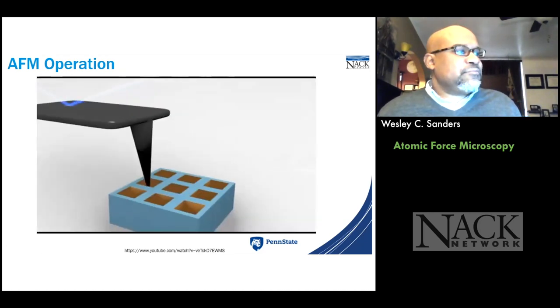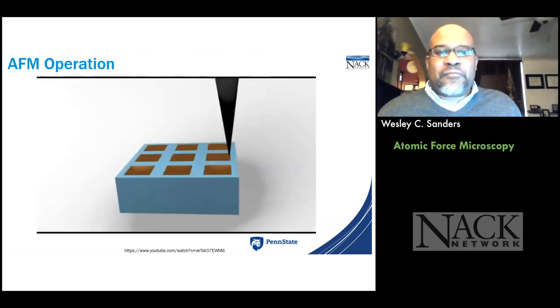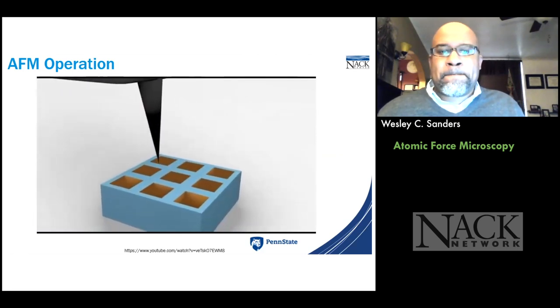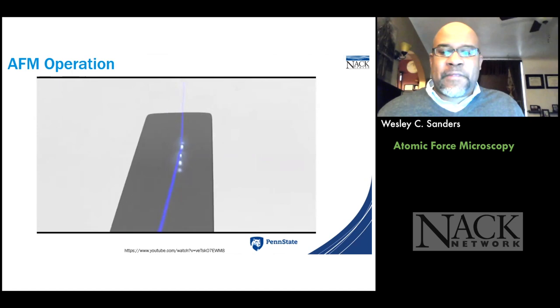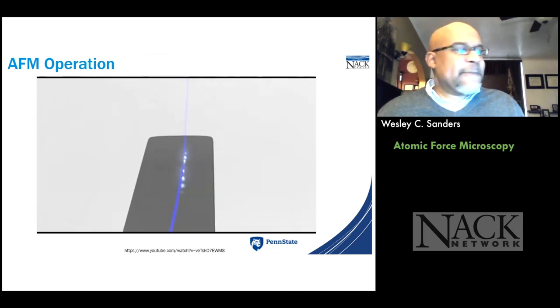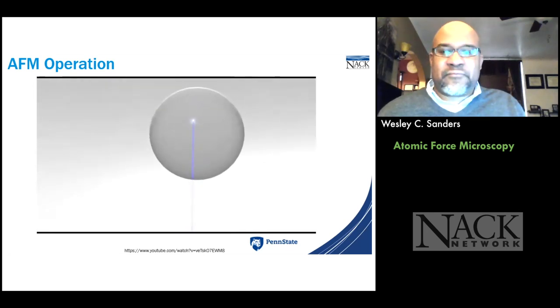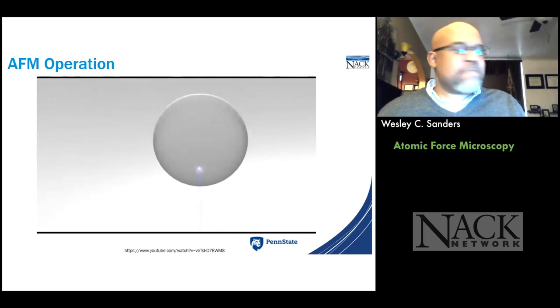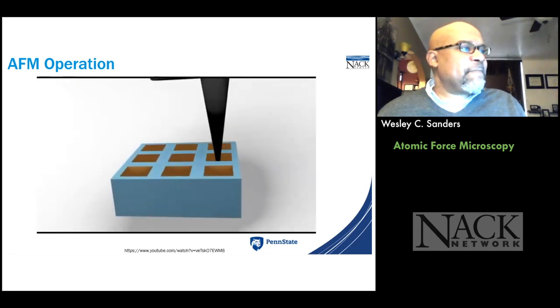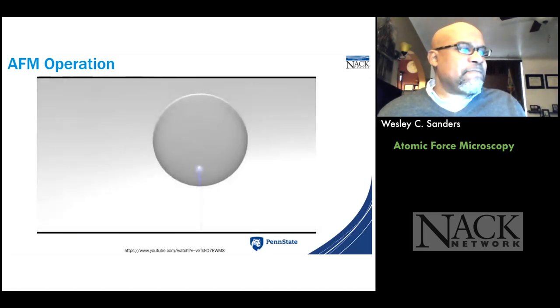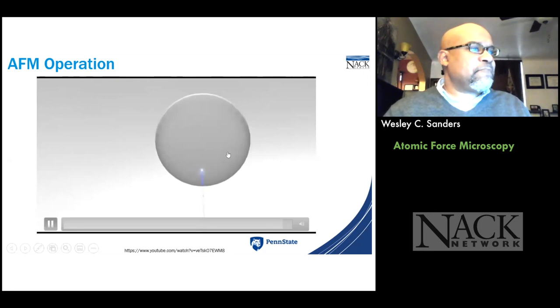This animation shows the basic principle of AFM in contact mode. A technique relies on feeling the surface with an extremely sharp tip — the radius can be below 10 nanometers — which allows surface features to be revealed at the nanoscale. The tip is attached to a cantilever whose deflection is monitored by the change in reflection of a laser beam onto a photodiode. As the tip goes into surface features, the angle of the laser beam's reflection changes, giving readings for scanning surface topography.